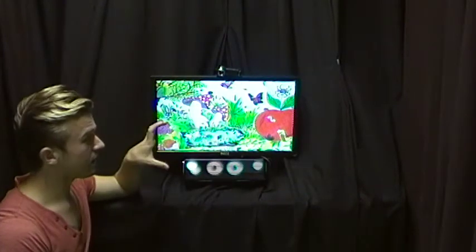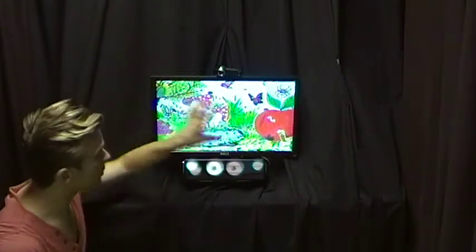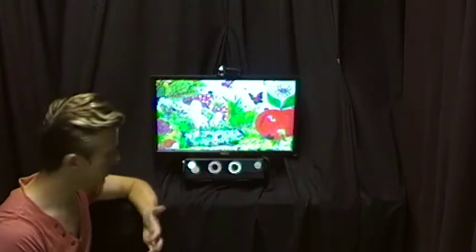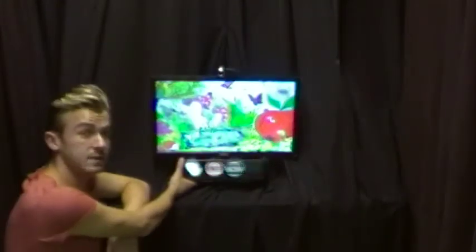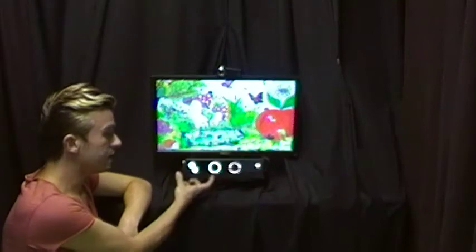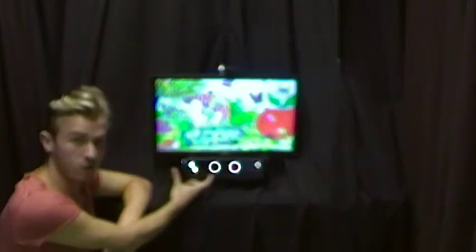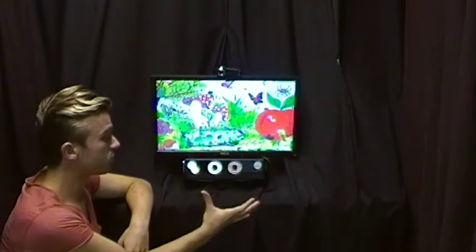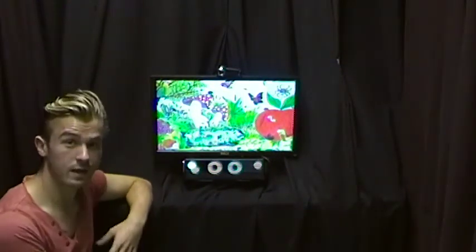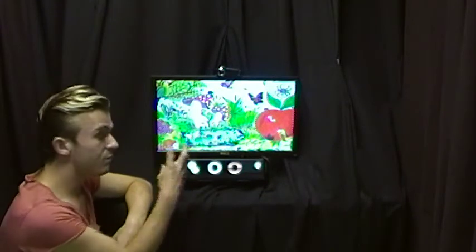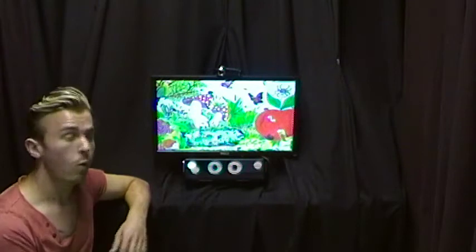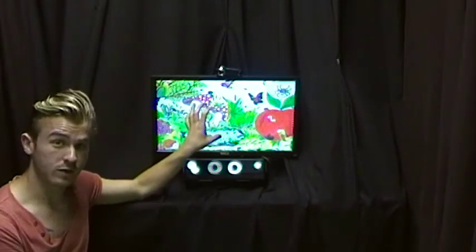So this is the eye tracking setup, and we can see we've got the screen here which displays the stimuli that you're going to show the child, and this box underneath is the eye tracker. The lights that you can see on the camera right now are infrared lights, so they're not visible to the human eye per se. So a child sat here just sees a black box, there's no light coming out of it that they can see. And that infrared light bounces into the eye and tells the eye tracker, the way it bounces out, where on the screen the child is looking at any one time.